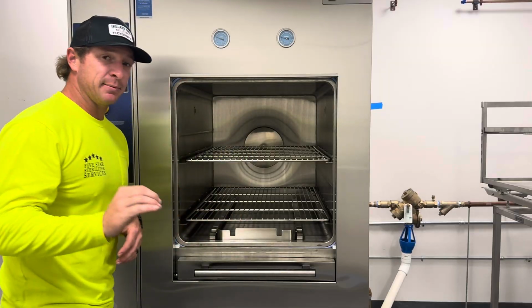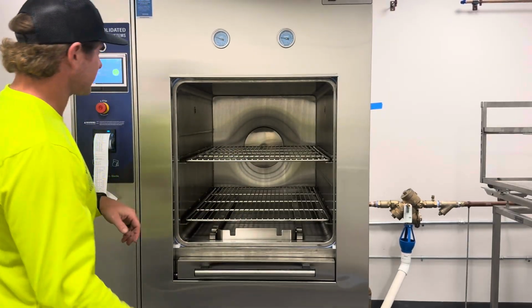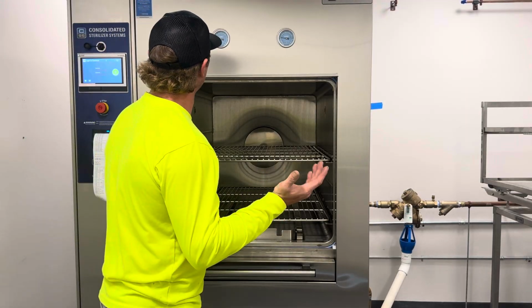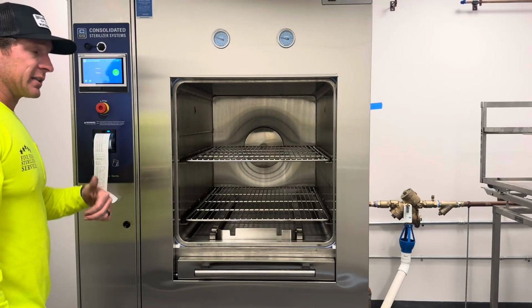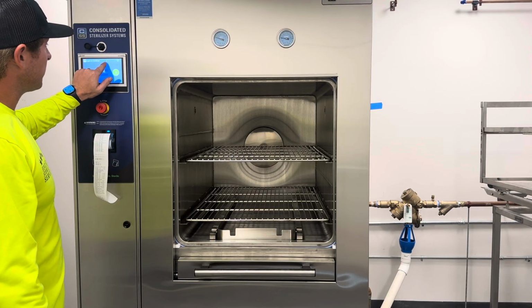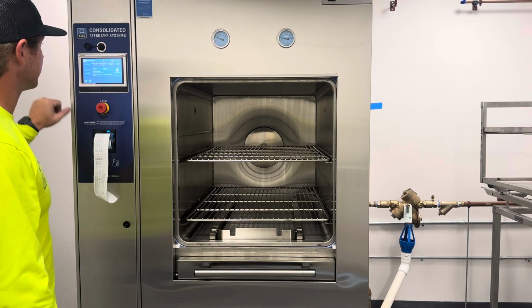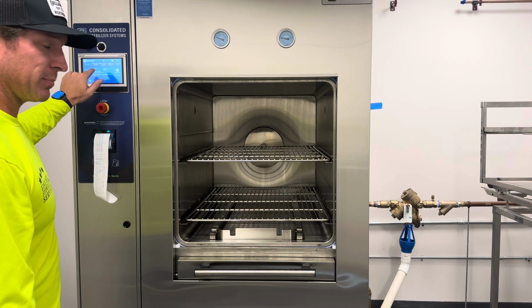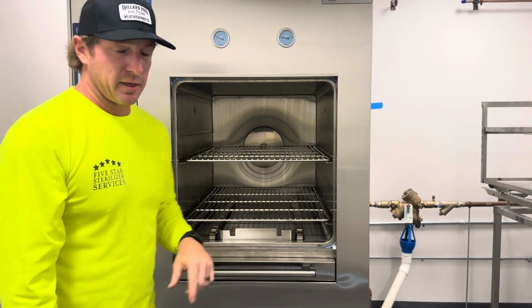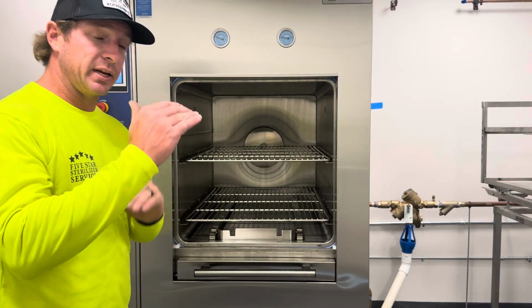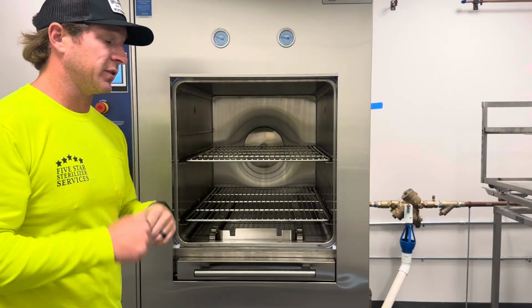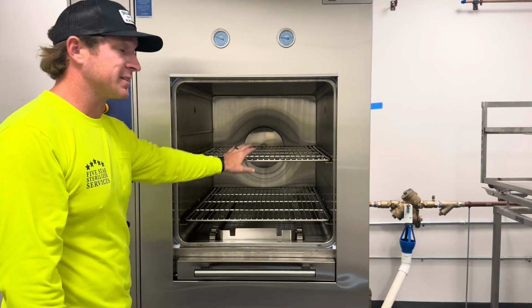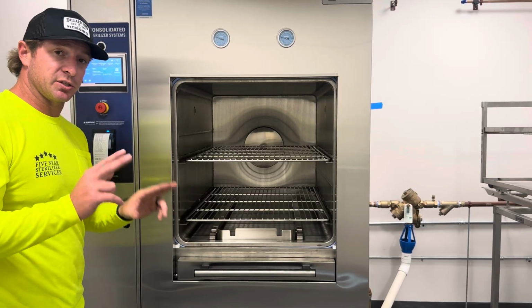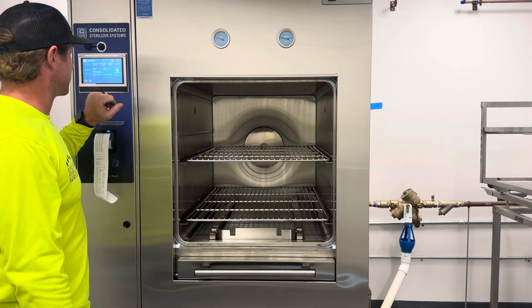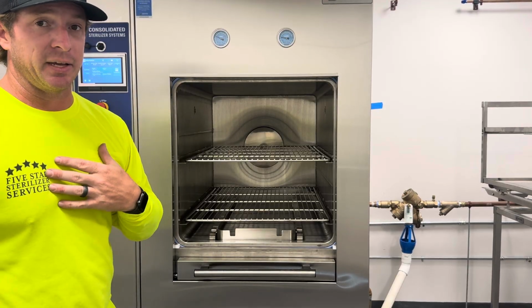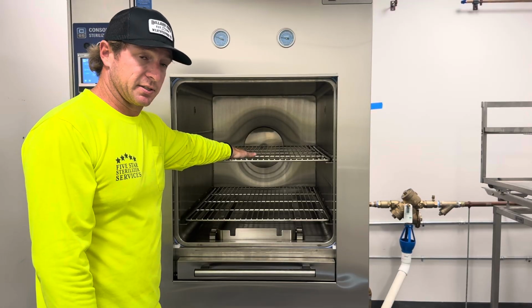We need a minimum of 10 psi in the jacket before you start. 10 to 15 psi normally. Right now it's operating at 14 psi. But how you would check to make sure that you are ready to run is you can press this information tab or button at the top of this screen, and it's going to display the chamber temperature, chamber pressure, and jacket temperature. The jacket temperature needs to be at or near your target sterilization goal. So if you're trying to autoclave or sterilize at 121 degrees, this jacket temperature needs to be plus or minus 2 or 3 degrees of your target. So right now it says it's at 119 degrees. That satisfies me if I want to run at 121 degrees Celsius inside this autoclave.